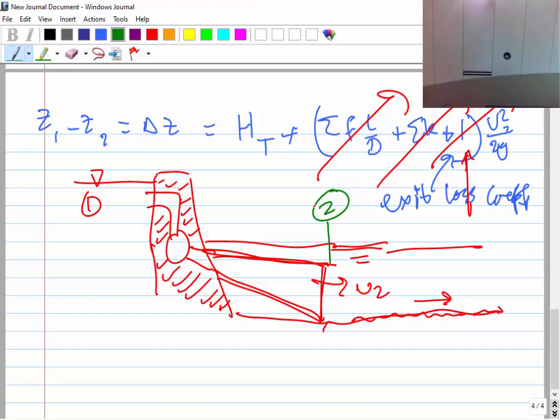So Jairus is saying, yes, if you add this draft tube, you didn't really change the velocity over here, but if you do Bernoulli between this place and that place, you will figure out that the pressure here is not atmospheric. Without the draft tube, the pressure here is atmospheric. But if we add this draft tube, the atmospheric pressure moves over here, and now this pressure is lower.